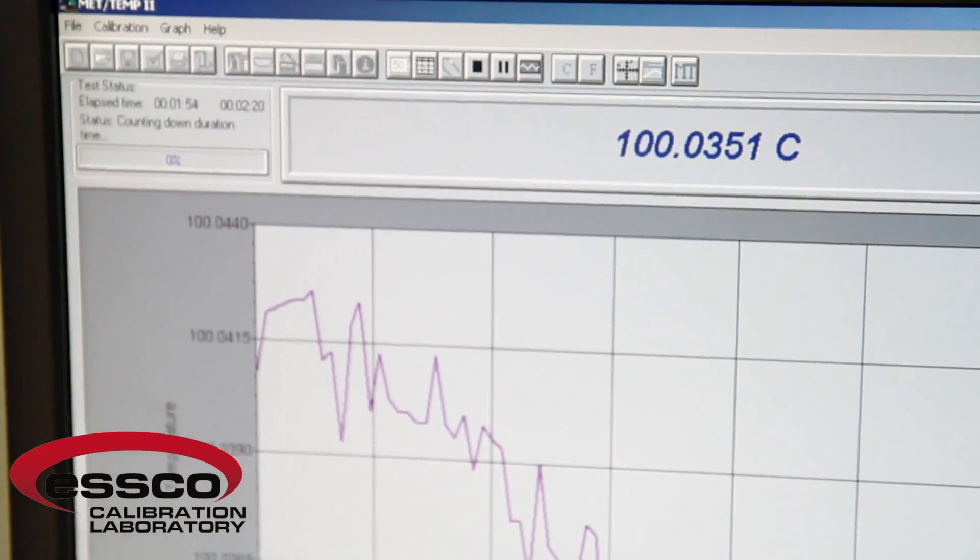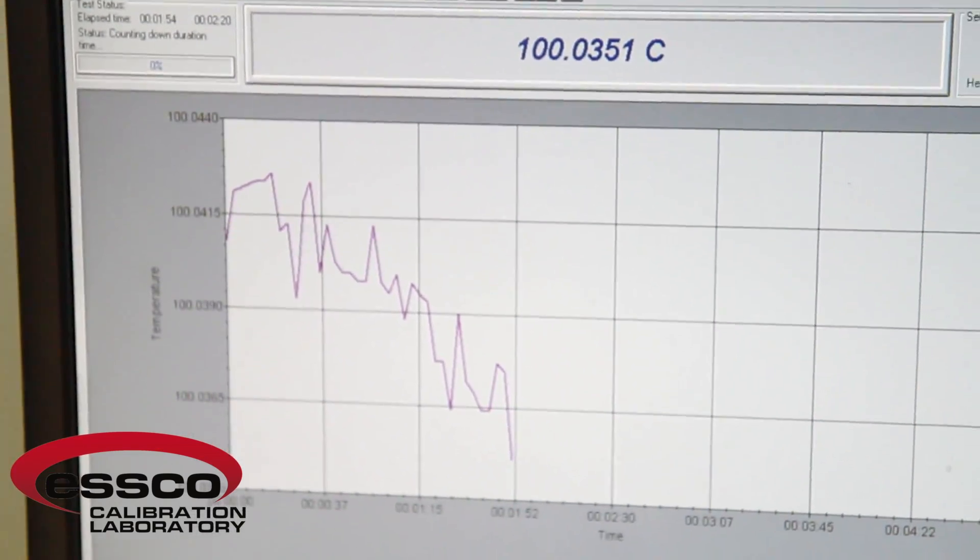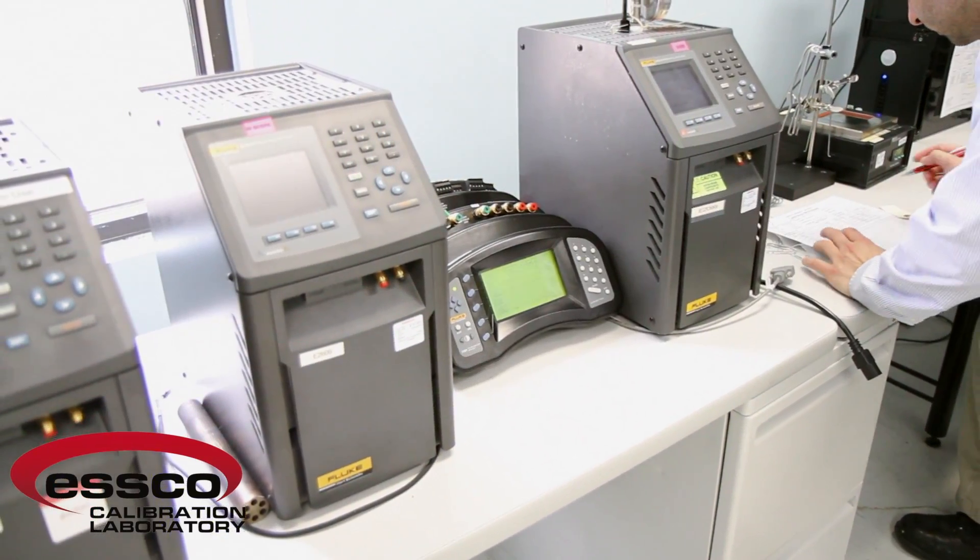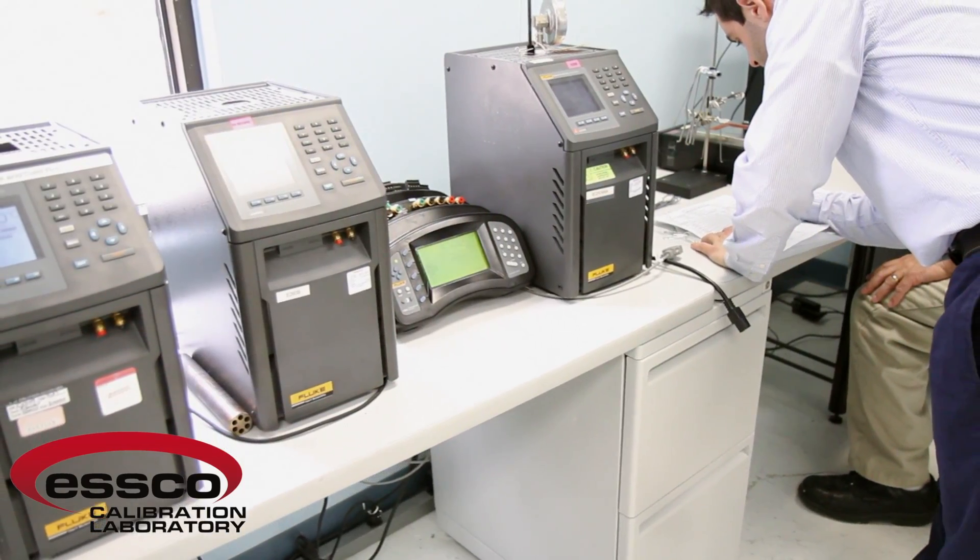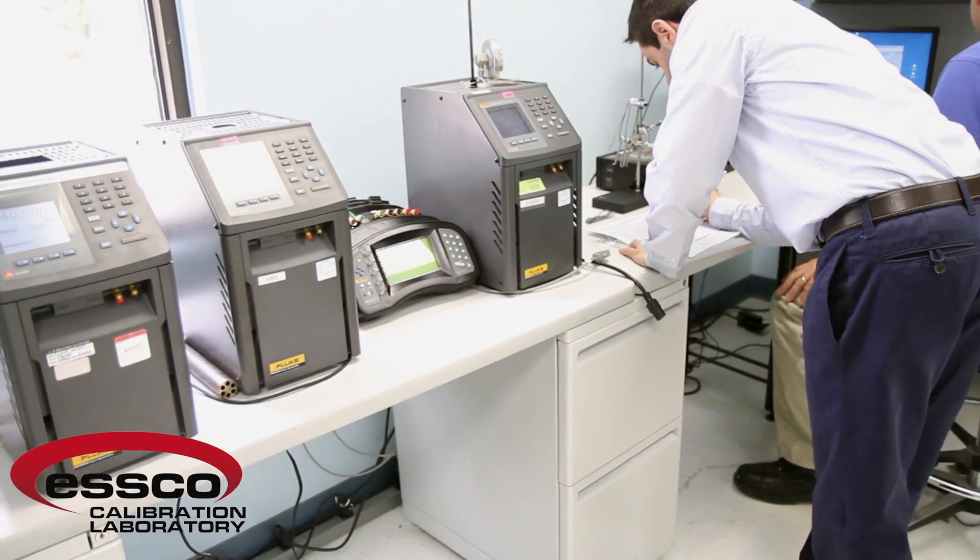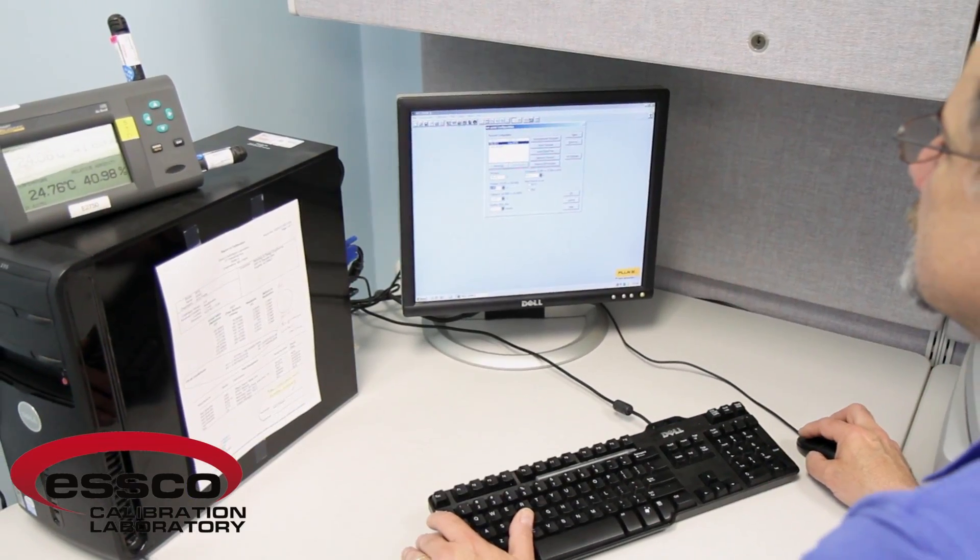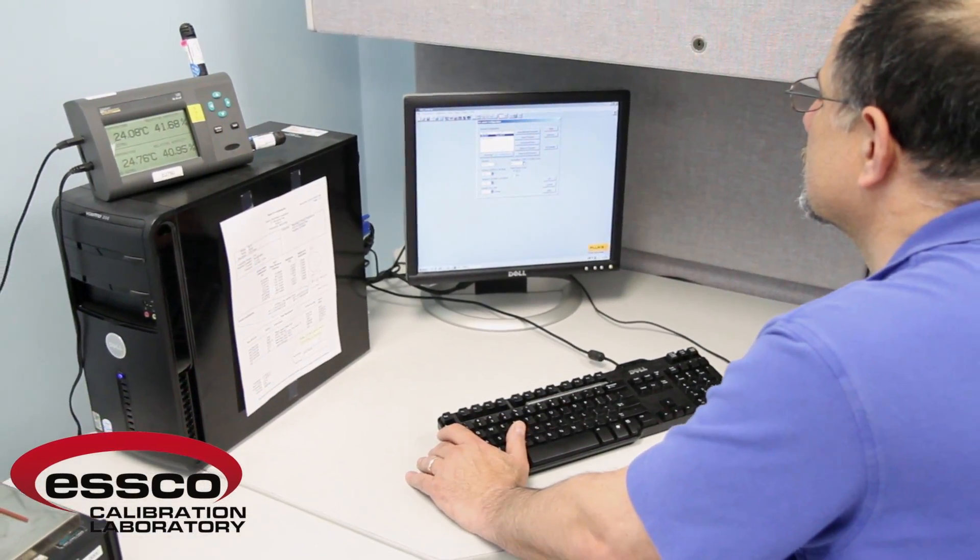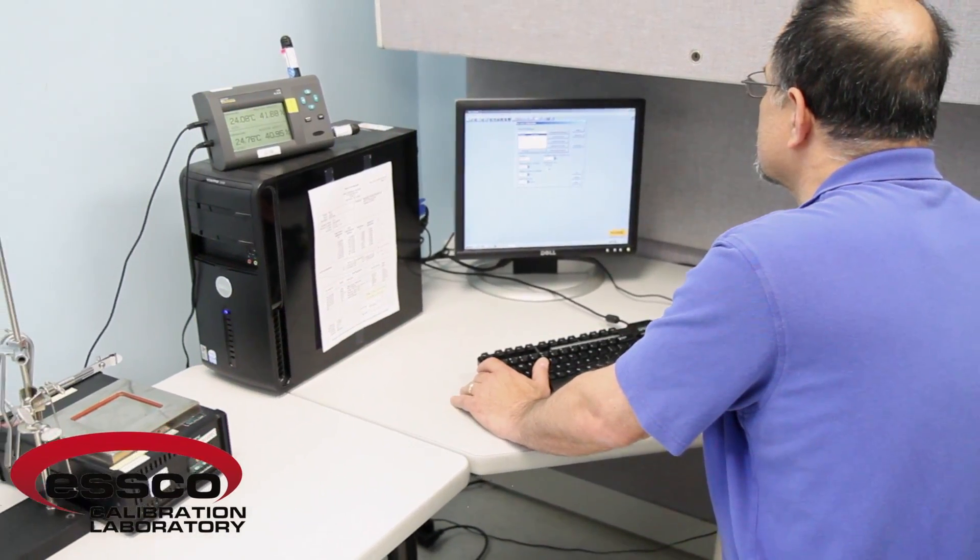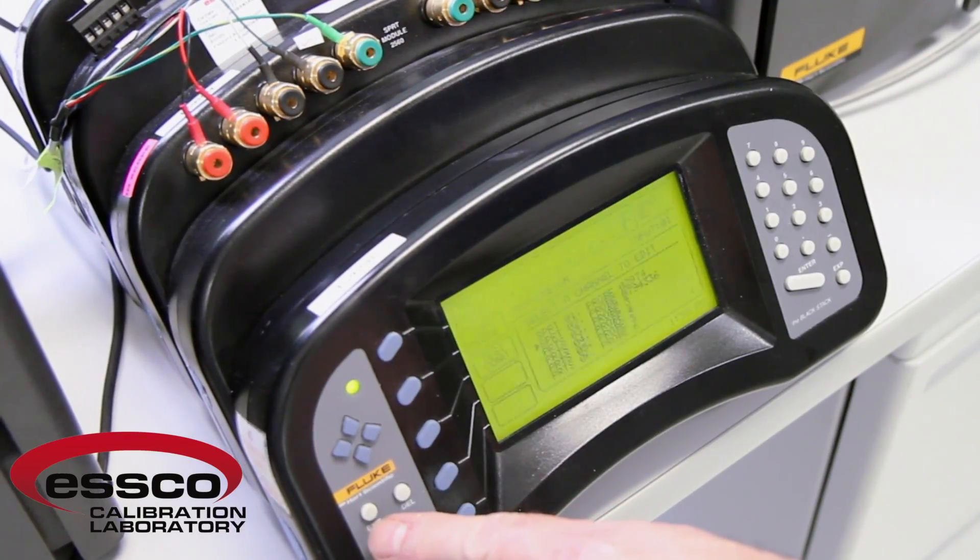Using the MetTemp software in conjunction with our Fluke Blackstack and Metrology Wells, we are able to provide customers with specific set points throughout the effective range of the instrument. This is extremely helpful for probes with a wide range, as the software is constantly monitoring the unit under test while the metrology well is acclimating to the chosen set points.